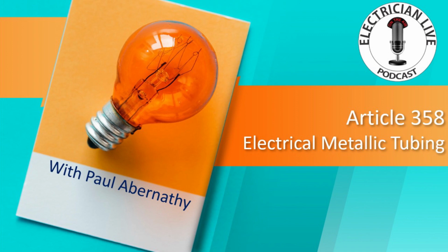Now, let's move on to the second one, and that is, what about aluminum EMT? Very common. It's making a big surge out there. There's a couple of companies that just produce aluminum EMT. It's really light. It bends well, and it is still EMT. It's still an EMT tubing product. But let's read what it says here in 358.10(B)(2), because we're in the corrosive environment part of Section 10.